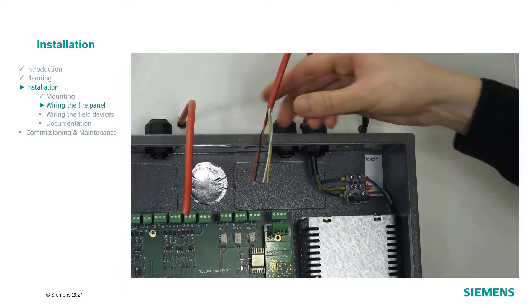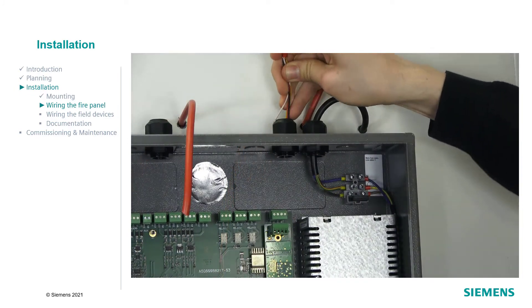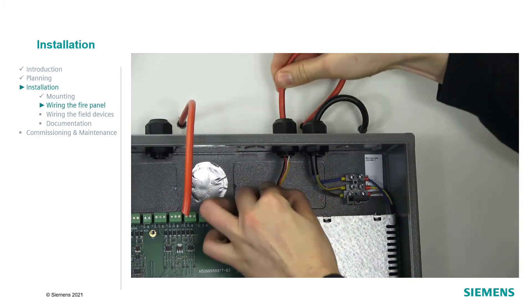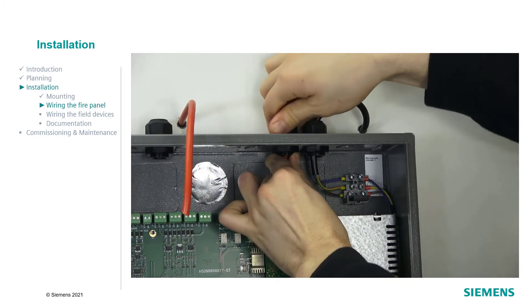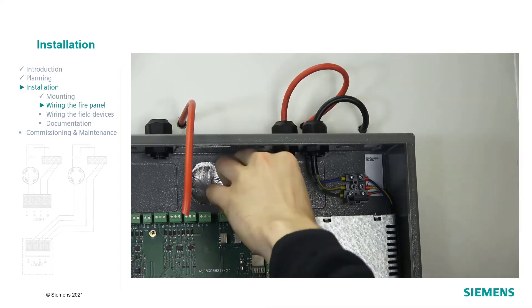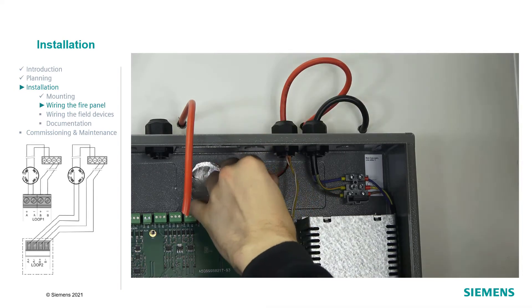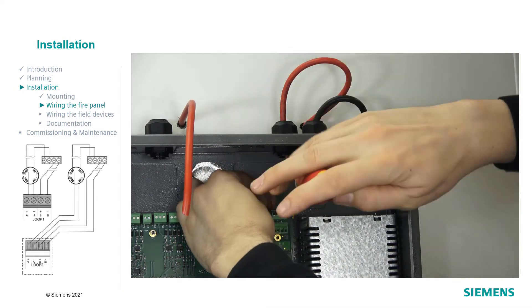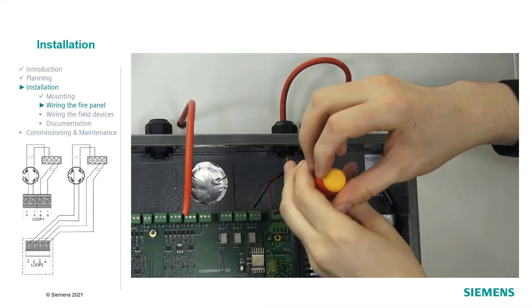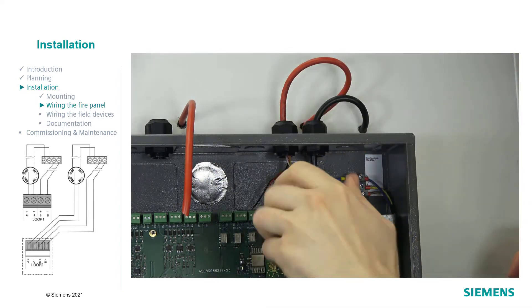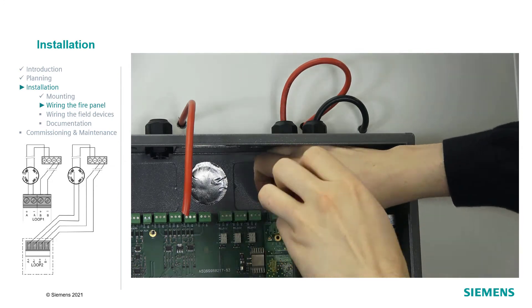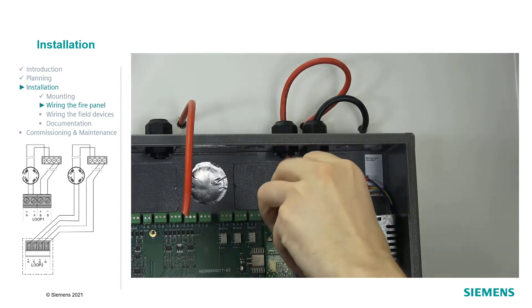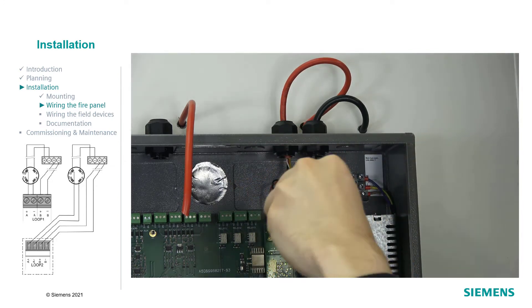Then connect the signal and control cable. After that, let's go on with the detector line. Connect the detector line to connector A. In case of a loop topology, connect the returning line to connector B.